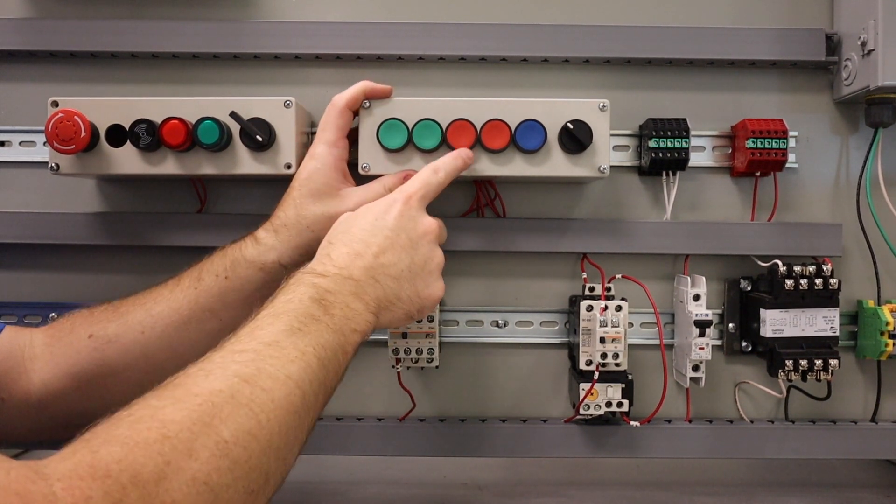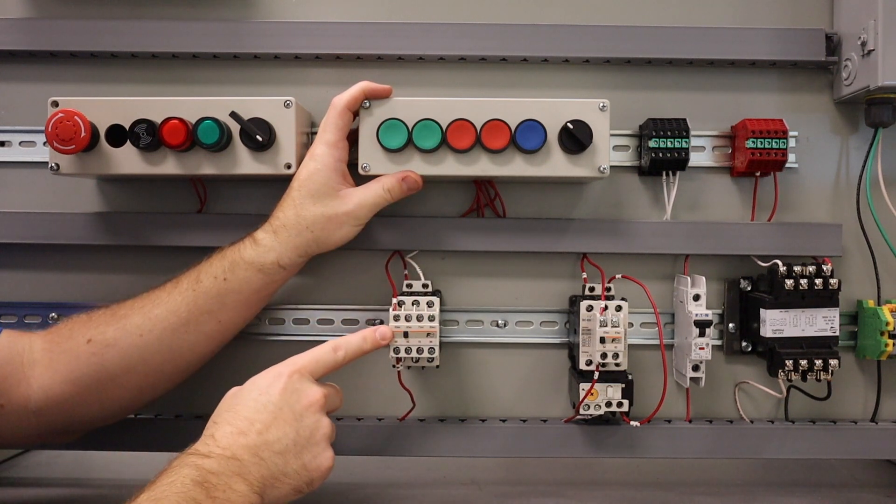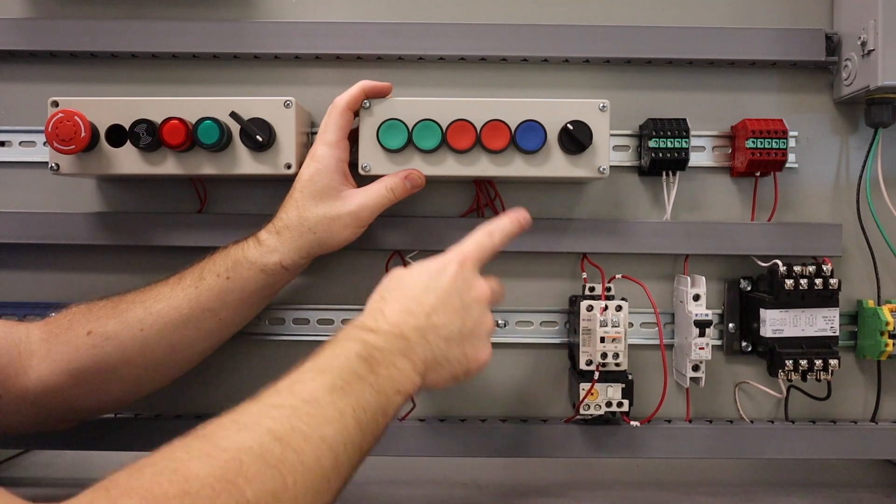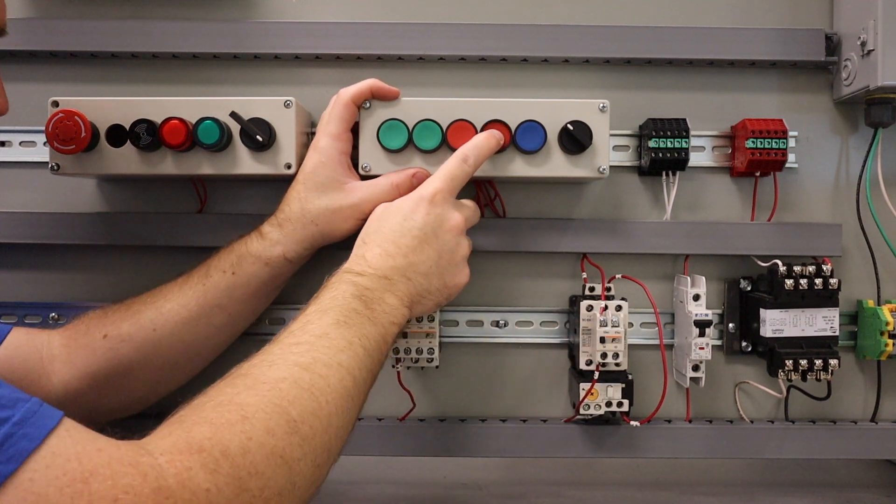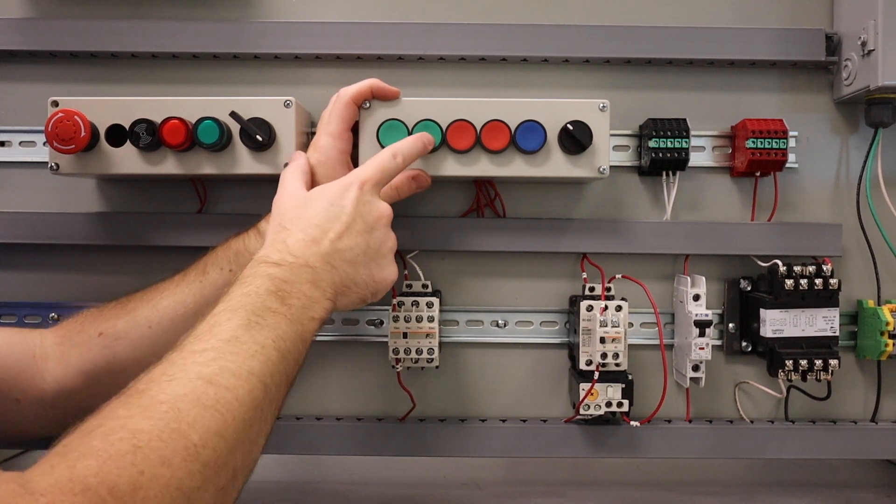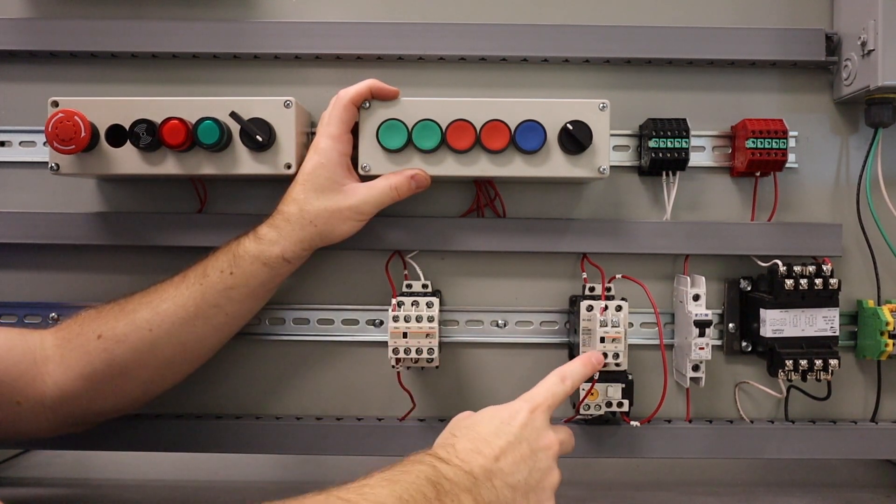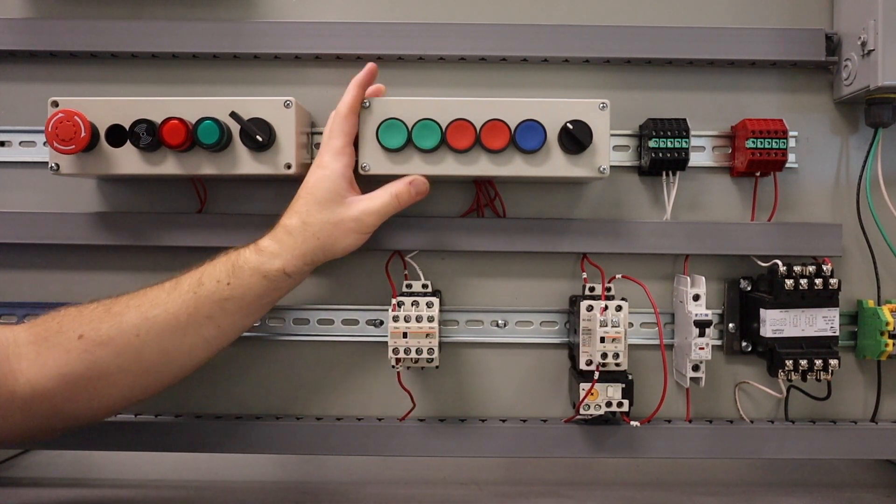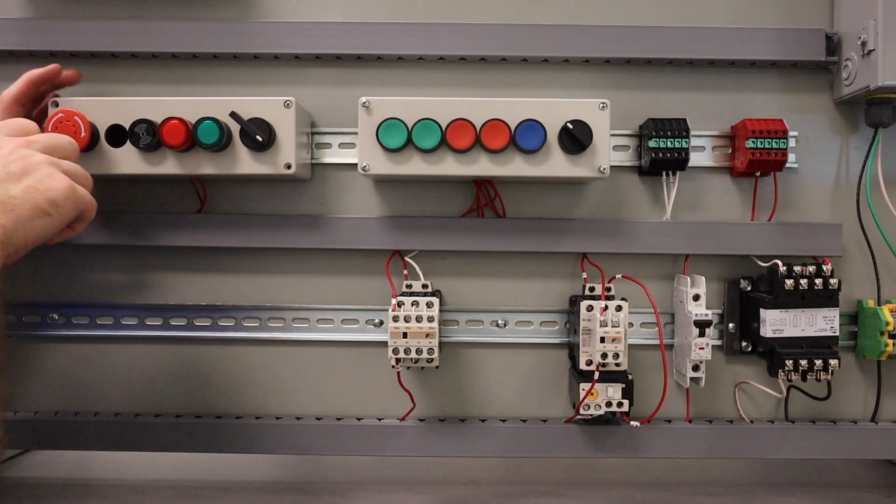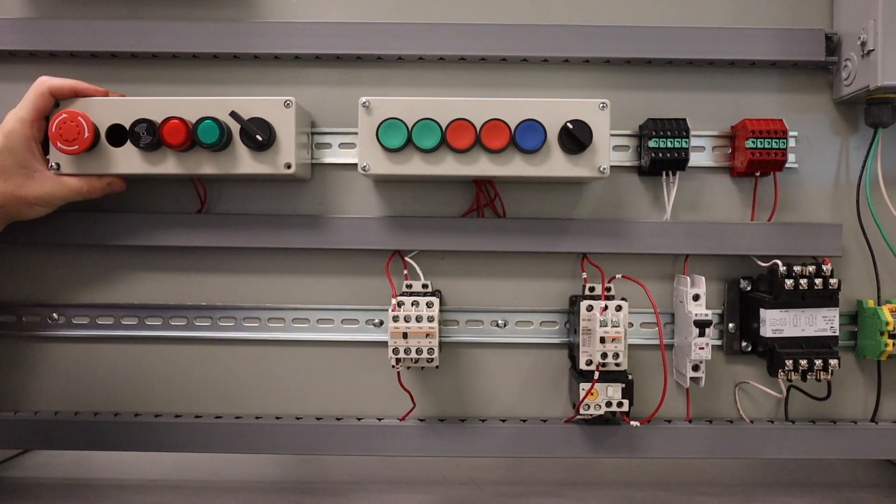If I press motor two, it's going to pull in. If I hit the motor two stop, it's going to stop. Now if I press this one and this one, you can see that they are both turned on right now. That's how the circuit works. If I hit my e-stop, it'll kill them both.